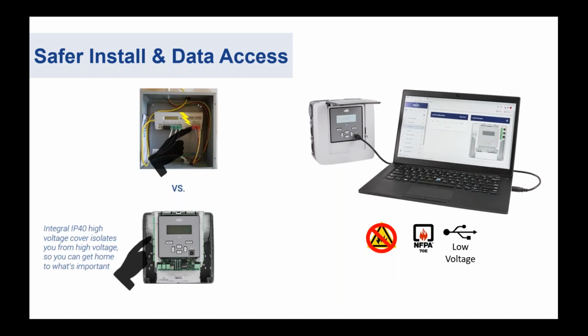Next, we took a lot of pride in making sure that we made a safe meter. The last thing we wanted to hear was someone getting hurt because of something that we designed and make. So when we took a look at some of the feedback from customers on the old Power Patrol, they'd always have to completely shut down the voltage to the panel because we had this exposed terminal block right at the front of the meter.